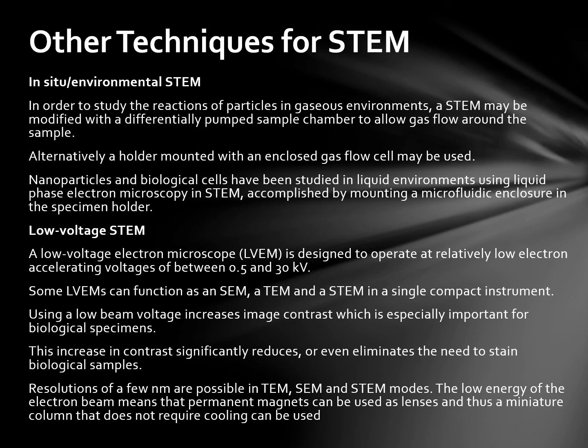Low-voltage STEM microscopes are designed to operate at relatively low electron accelerating voltages of between 0.5 and 30 kV. Some LVEMs can function as a SEM, a TEM, and a STEM in a single compact instrument. Using a low beam voltage increases imaging contrast, which is especially important for biological specimens, and significantly reduces or even eliminates the need to stain biological samples. Resolution of a few nanometers is possible in TEM, SEM, and STEM modes. The low energy of the electron beam means that permanent magnets can be used as lenses, and a miniature column that does not require cooling can be used.